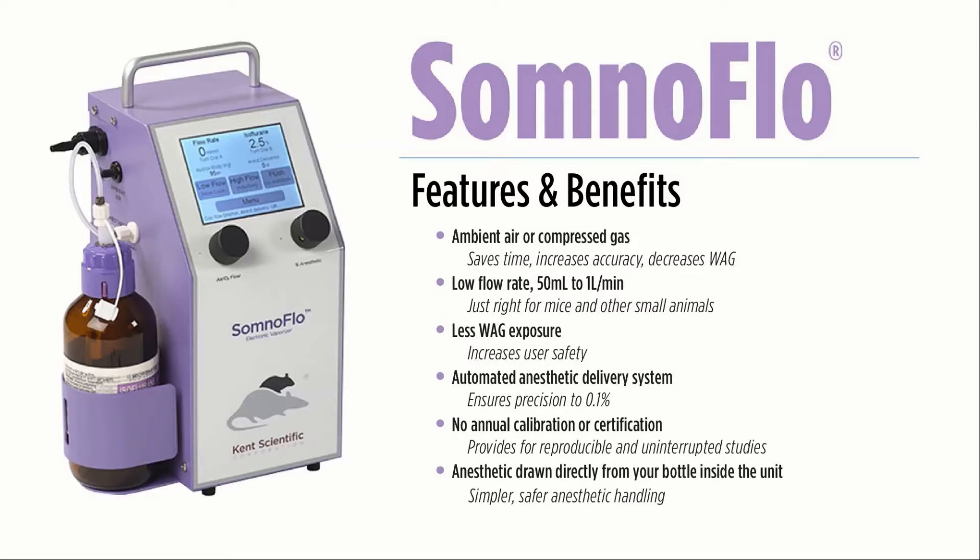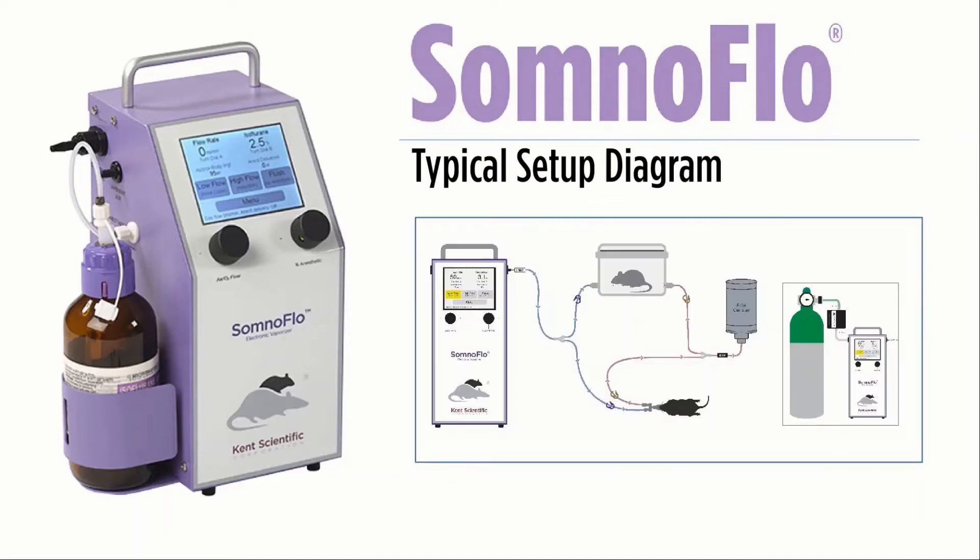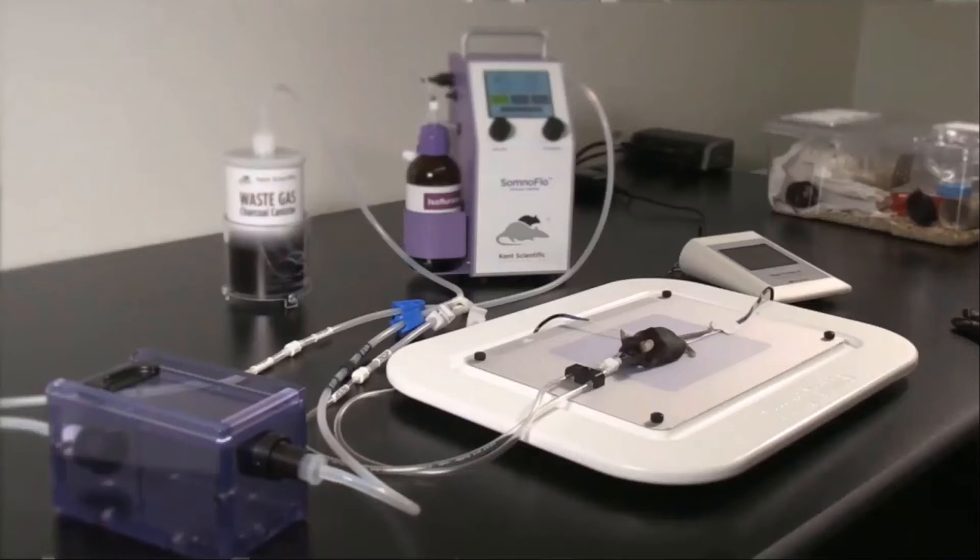There's no annual service calibration requirement, ensuring accurate anesthesia delivery and precision up to 0.1%. The SomnoFlo low-flow electronic vaporizer is safer for you and your valuable animal research models. The labeled tubing makes setup a breeze — simply attach the inspiratory tubing from your SomnoFlo controller to your induction chamber and nose cone, as illustrated in the diagram on your screen.